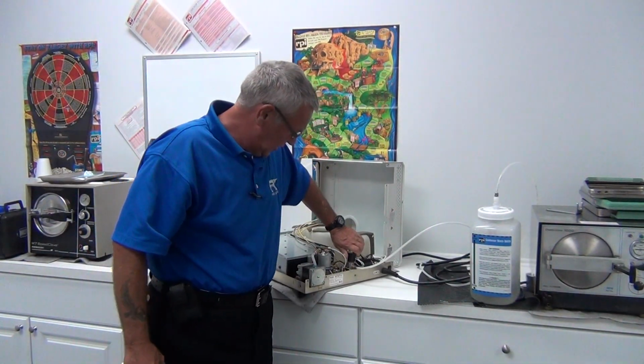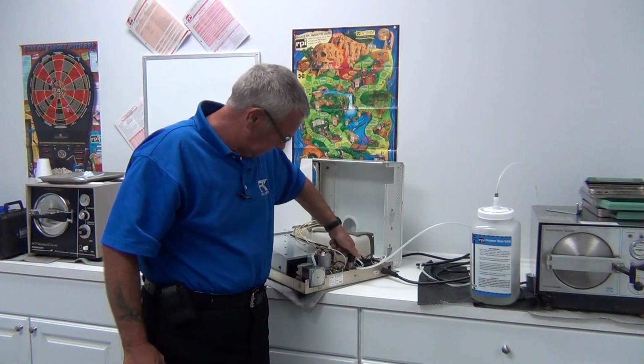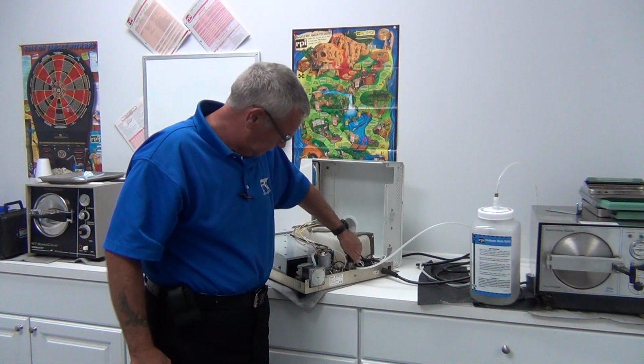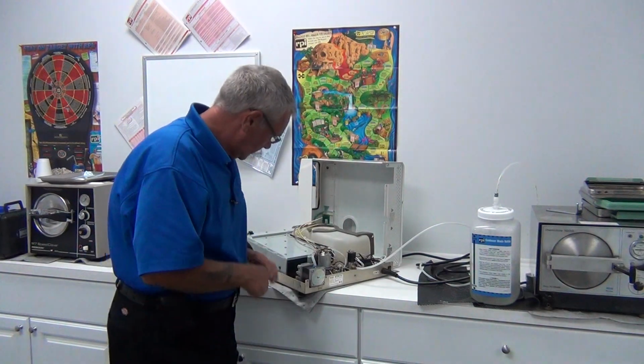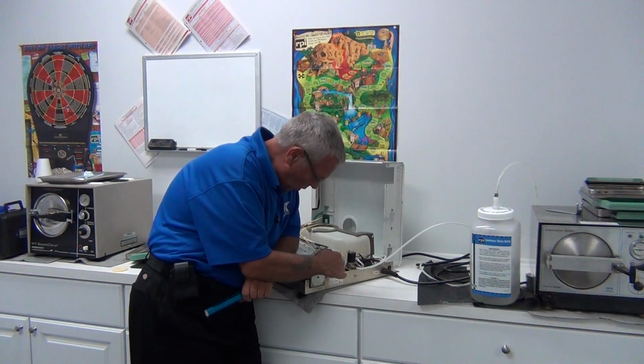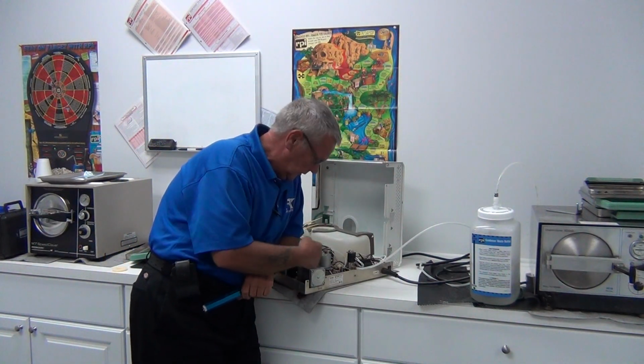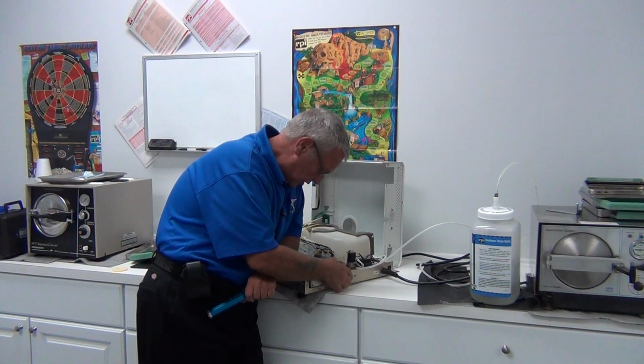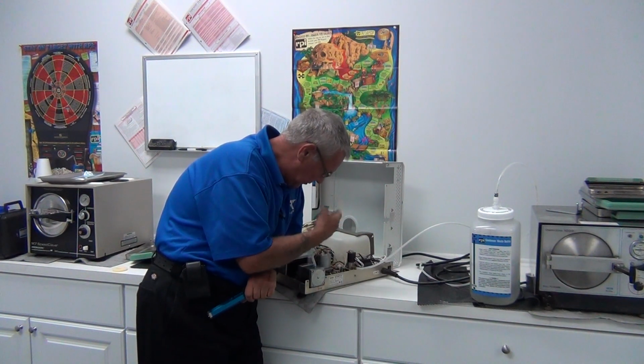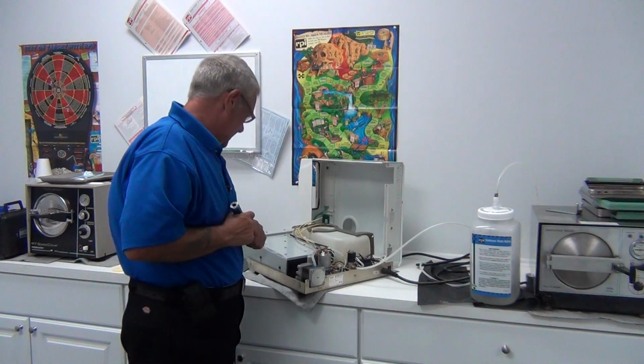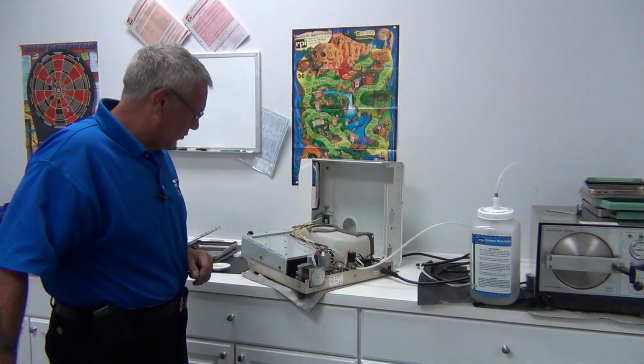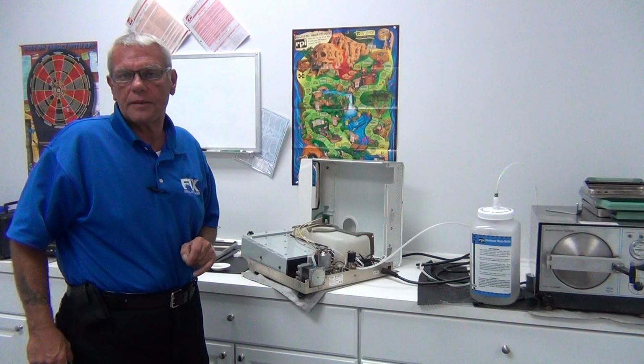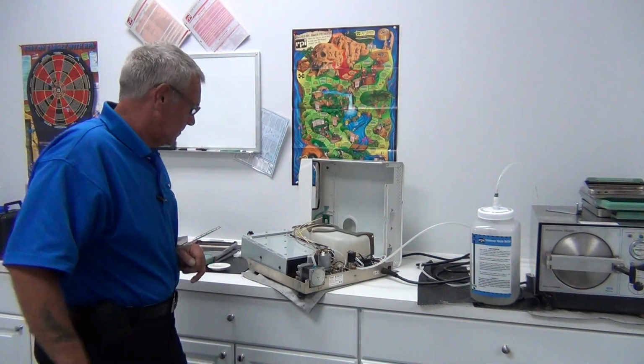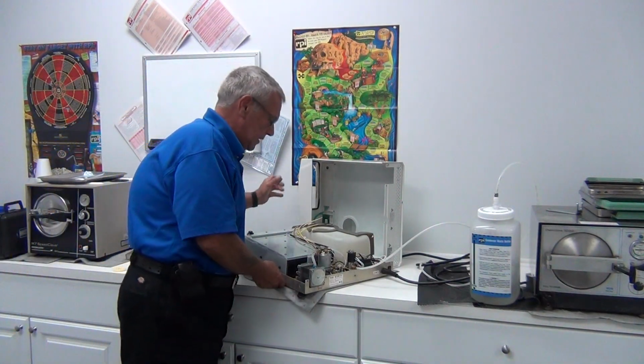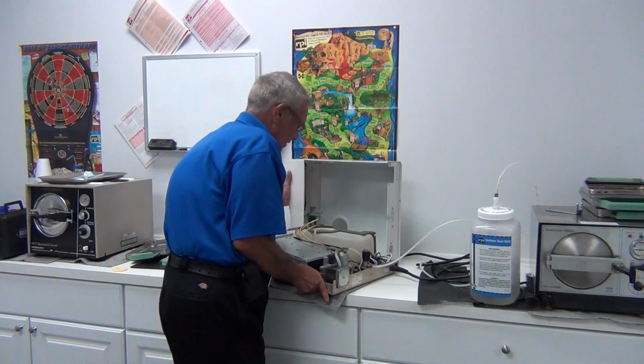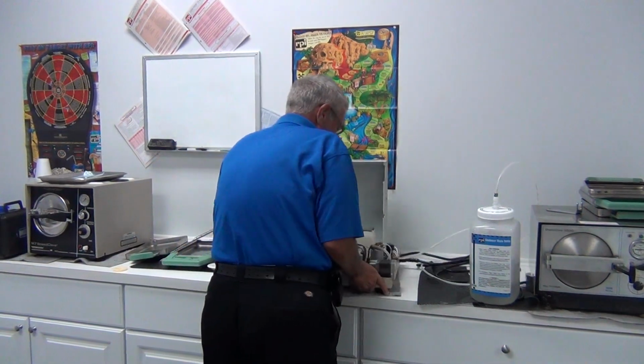Okay, we've reassembled our solenoid. Checked our boilers for stains, watermarks. Looked at our electrical components for scorches, shorts. Everything looks fine. The machine looks clean. I see no stains on the platform, no evidence of water leaks or extreme steam leaks.